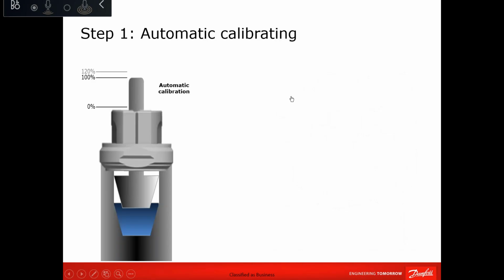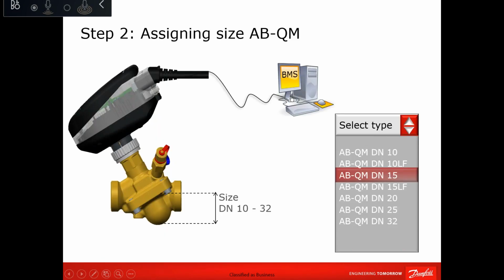So if we take automatic calibration, it's very simple. First time you energize or when you hit the reset button, it will go to full close, full open to know what is the total modulated stroke length. Assigning the size is based on the application. So in this case, you can put our valve model, ABQM DN15, and so on, but this is also more flexible. You can name this actuator and valve any name you want. You will find in the list, like you see the sizes of the ABQMs here, at the end, user defined. When you put user defined, you can put any name, let's say FCU ground floor shop number 1 or FCU bedroom or living room, anything. So it's flexible. It shouldn't be the size, the ABQM size itself.